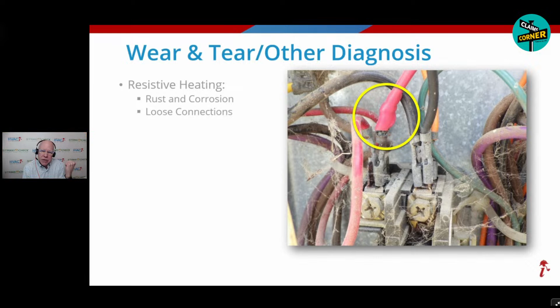What about acidic refrigerant? So what this technician is doing here is opening the service valve. They started with a little acrylic tube that had yellow pH paper in it. They ran a little bit of refrigerant over it - if it changes colors, there's acid in it. That's the same pH type test you would do for your soil out in your garden, to know whether it's neutral or acidic soil.